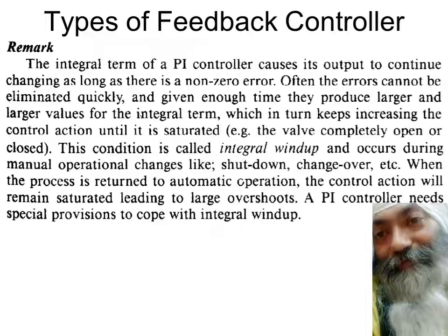My dear friends, I told you that because of the PI controller, the output will continue to change as long as there is a non-zero error. It doesn't become equal to zero, so this error cannot be quickly eliminated. It's going to take time, as in the case of filling up the vessel. Because of this, the output will keep on increasing and it is saturated. A valve may be completely open, but the output may continue to increase even after the valve is completely open. And this particular phenomenon is called integral windup.